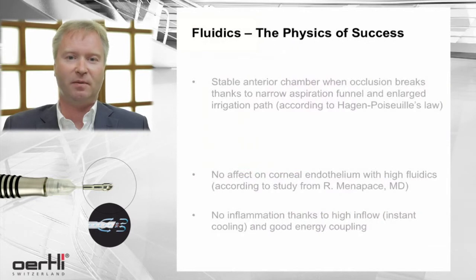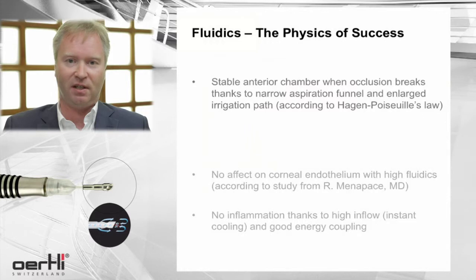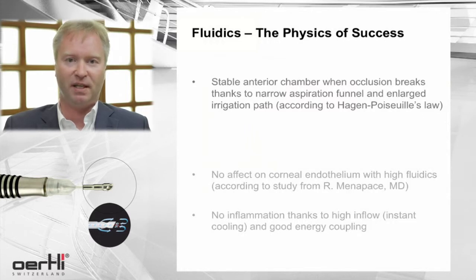High fluidics can be applied safely because of the laws of physics. Hagen-Poiseuille's law shows that if you create a capillary — a narrower aspiration funnel — then you are not at risk of surge if the occlusion breaks.